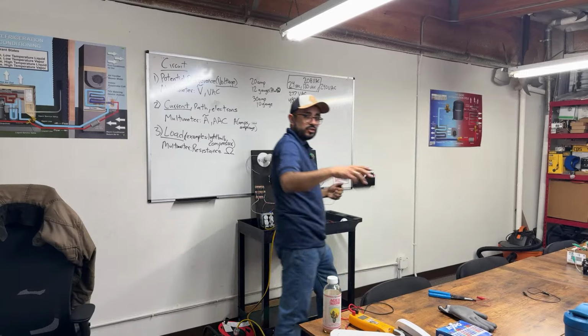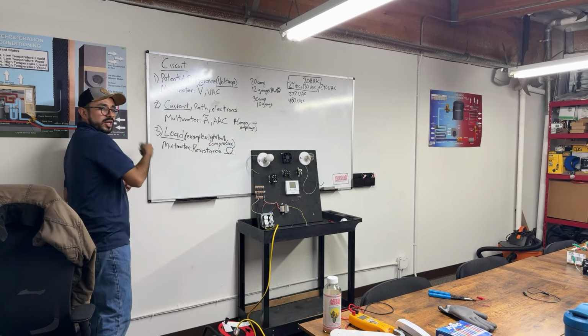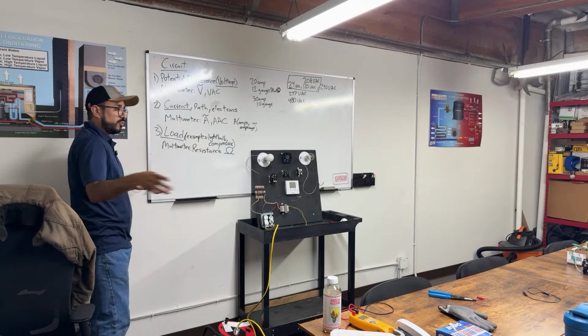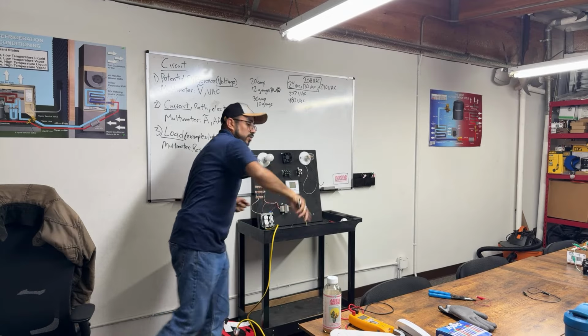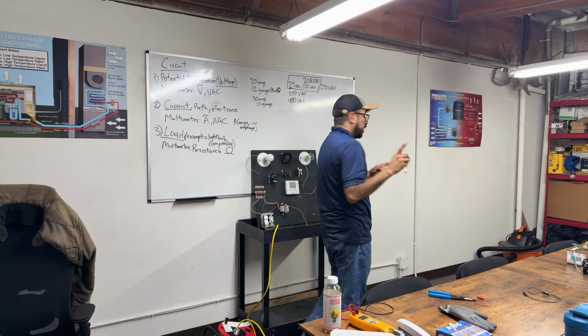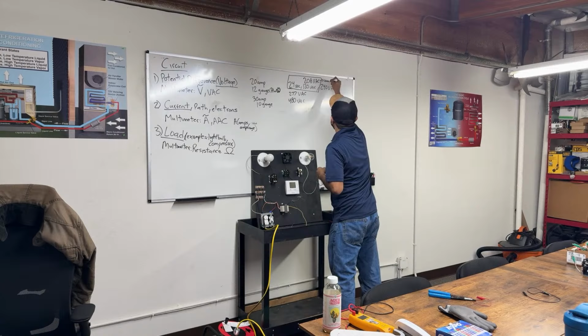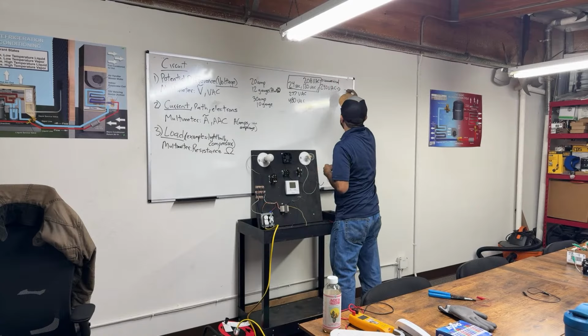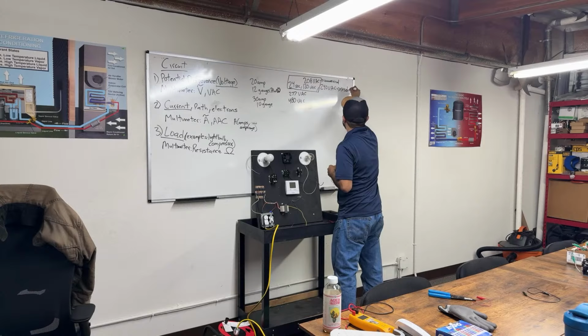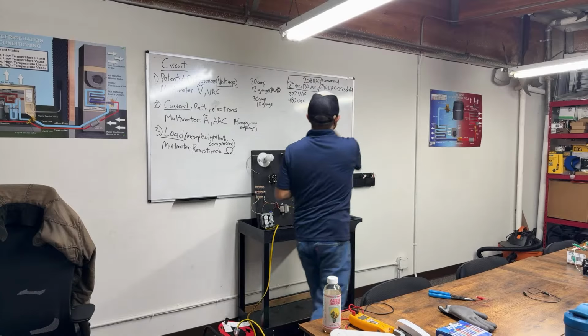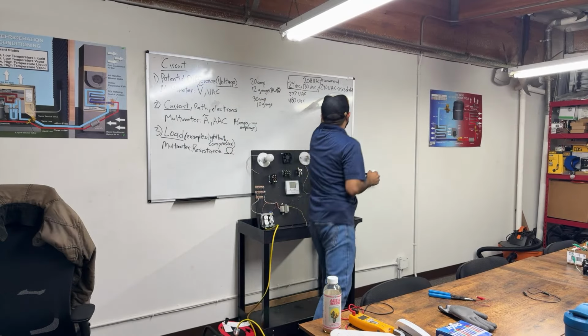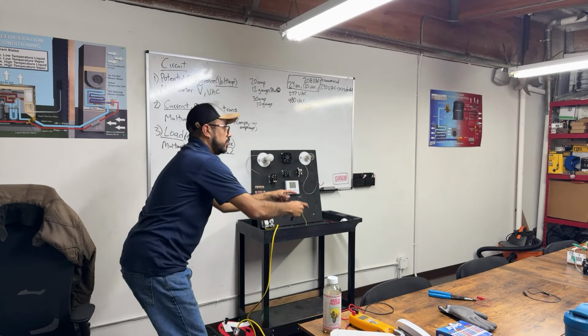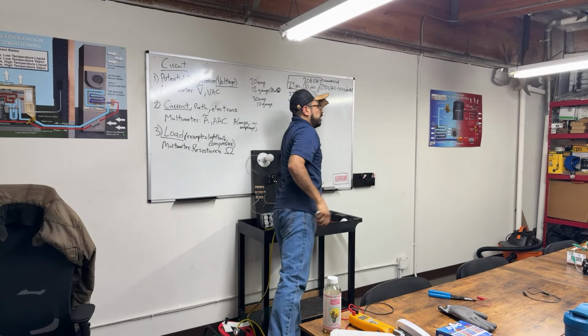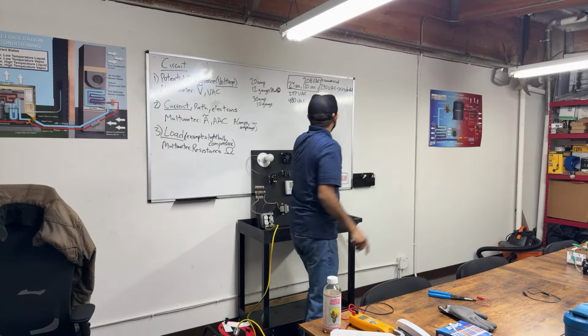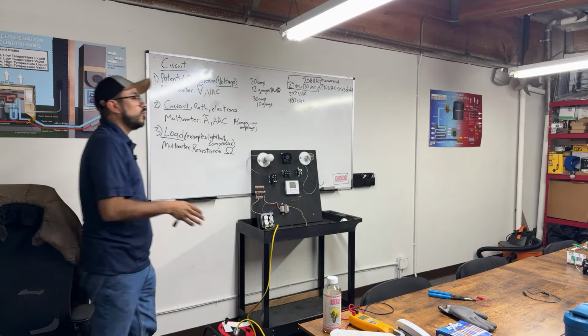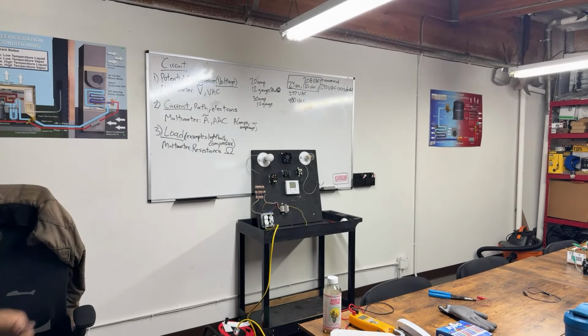The 120, that's your furnace power, right? When you connect power to your outlet, the furnaces are 120. The condensers that spin, or the package units in commercial buildings, are 208. In residential, because you have high voltage, it's 240. So this residential, you know the power that goes to your panel? Right there, it won't be 208, it will be 240 because it's residential. In commercial buildings, it's 208. That's the way you know it's commercial or residential. That's how you'll know.